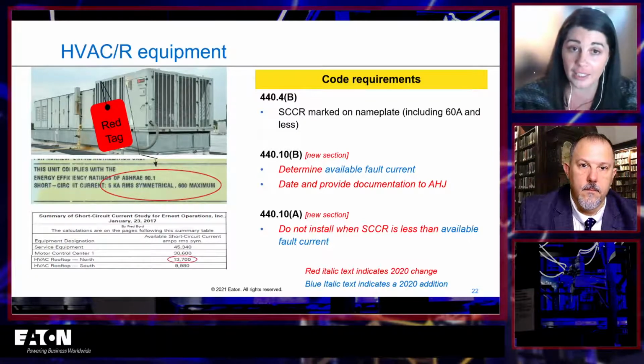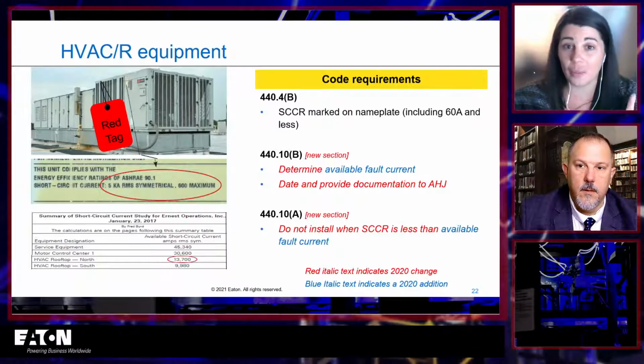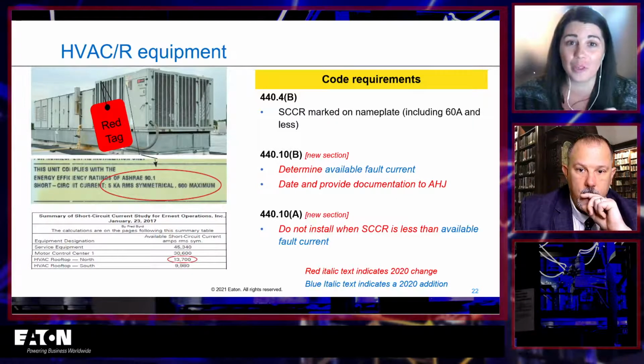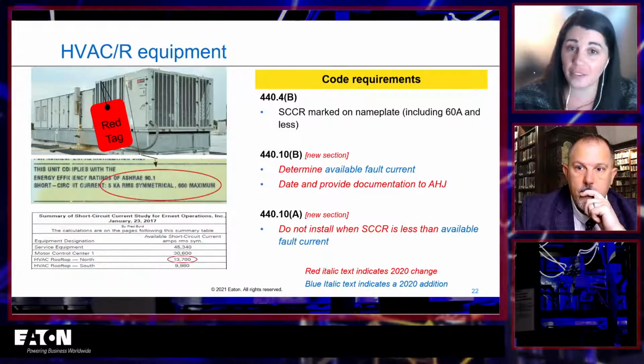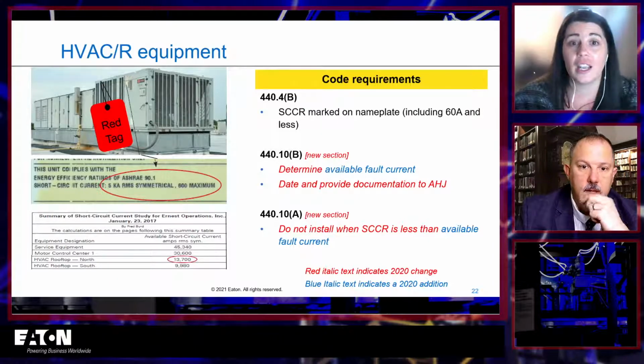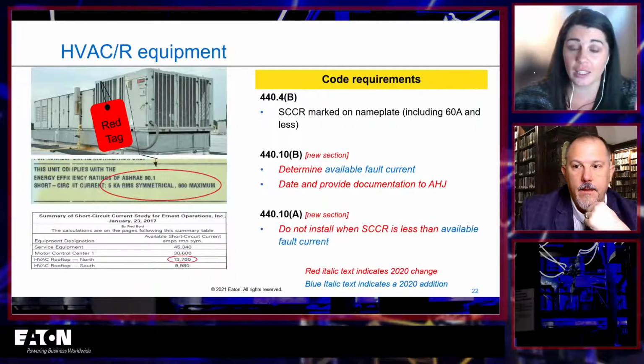Everything else has to have an SCCR. And generally, they're pretty low. That's why we see a lot of problems with these. Got to determine that available fault current and then don't install where the SCCR is less than the available fault current.